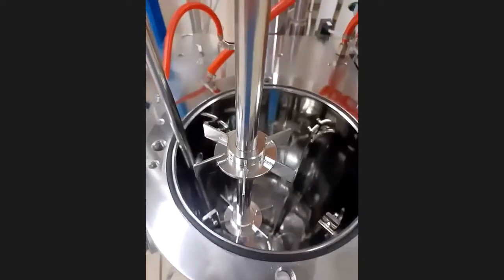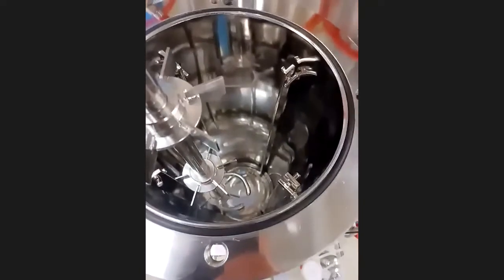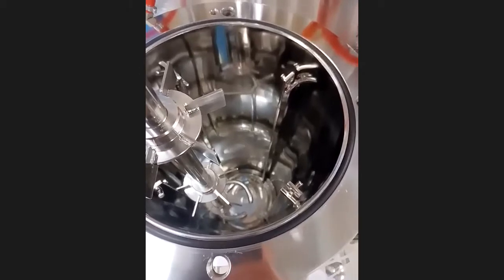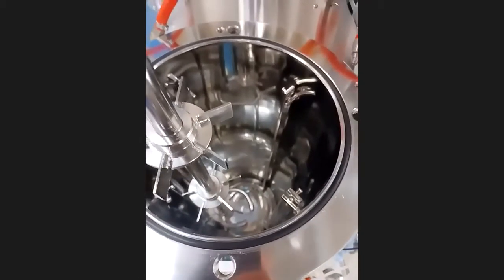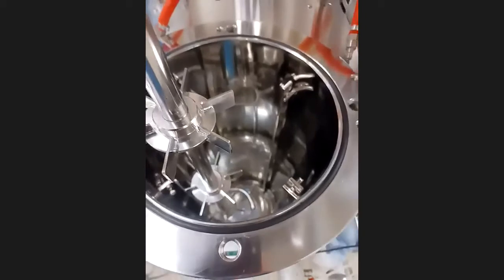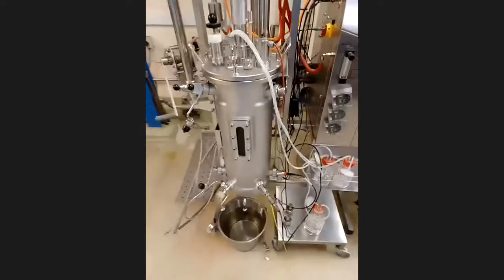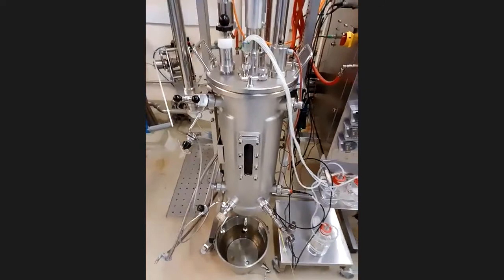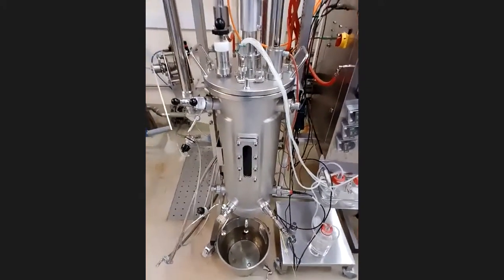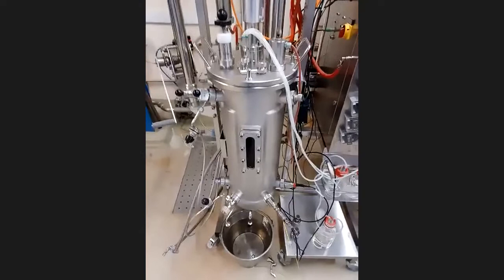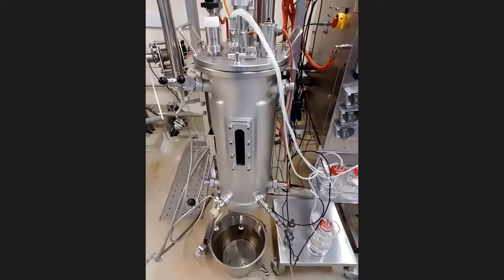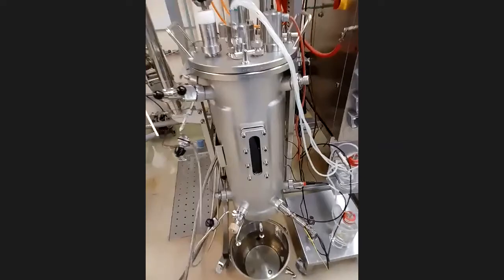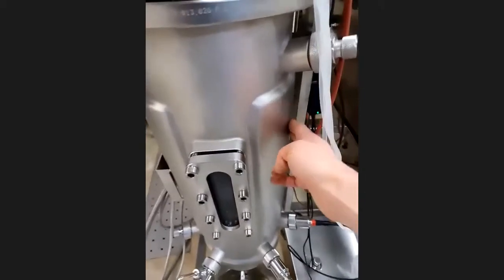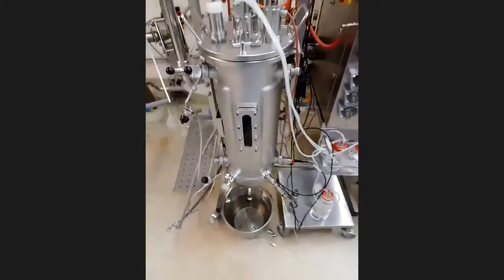And inside there, I don't know if I can actually see right at the bottom, is something that looks a bit horseshoe shaped, okay? And that, as horseshoe shaped, is the sparger. And that sparger bubbles air into the bottom of this reactor to provide the cells with the oxygen that they need to grow. So we charge this vessel with the media that provides the carbon and the nitrogen they need to grow, and then we sterilize it, okay? So typically for sterilization, we use steam that gets put into the jacket section, which is here, okay? And heats the contents up to 121 degrees.